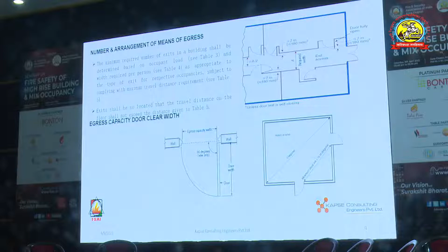So which direction? In a room which is of an X area, if I need to provide 2 doors, what is the distance between those 2 doors? Whether I can provide 2 doors next to each other, or I should provide there, or I should provide here. There is a code to it. So you measure the diagonal distance divided by half. The distance between 2 doors should be more than half of the diagonal distance. Okay, so there are a lot of insights in designing a building in terms of means of egress.